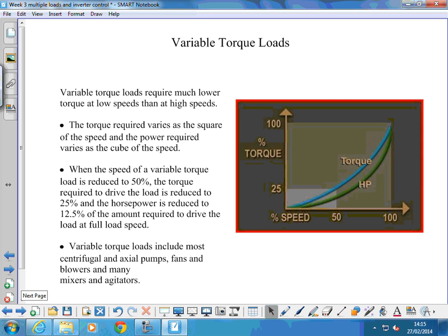If we look at a variable torque load, variable torque loads require much lower torque at low speeds than at high speeds. So the torque required varies as the square of the speed, and the power required varies at a rate of the cube of the speed of the motor. So when the speed of a variable torque load is reduced to 50%, the torque required to drive that load is reduced to 25% of what it is at full load, and the horsepower, or the power required, is reduced to 12.5% of the amount required to drive at full load speed. So remember, if it's requiring less power, you've got to put less power in, because you only get out what you put in. So you must be using less energy, less watts.